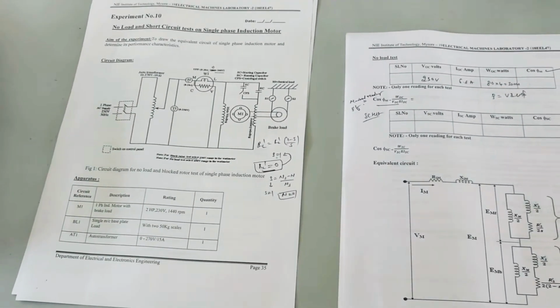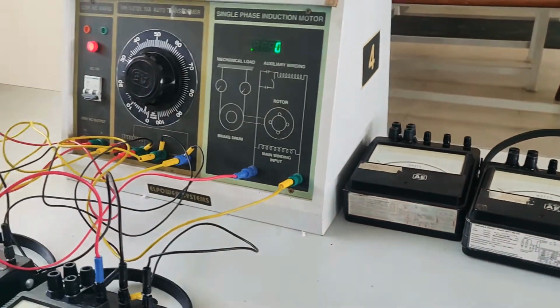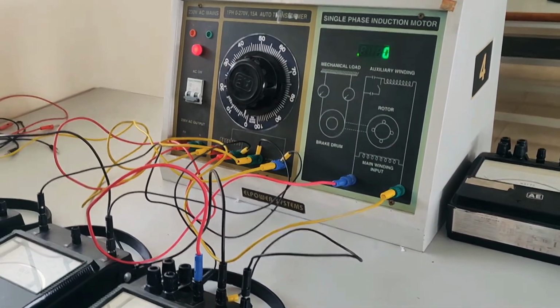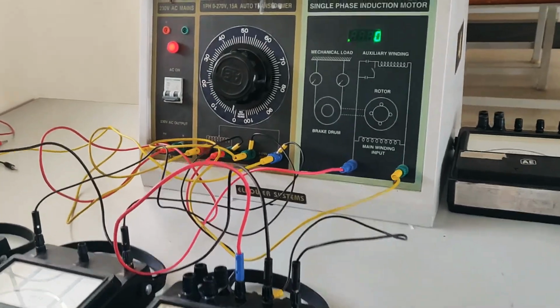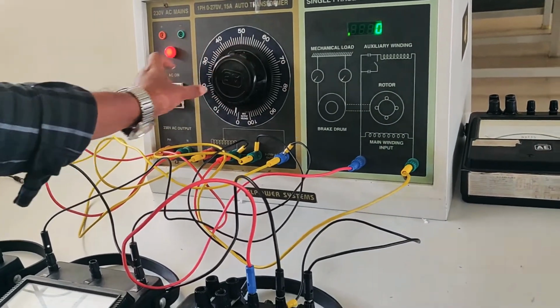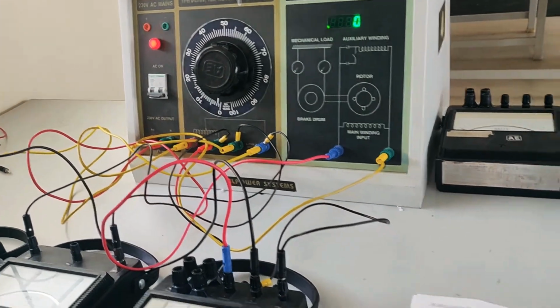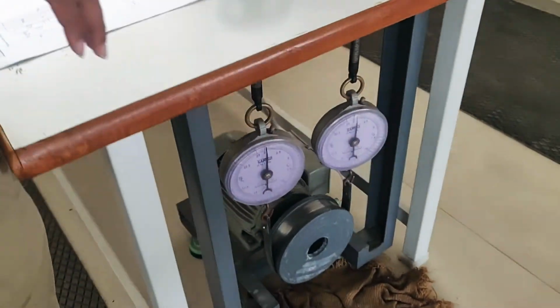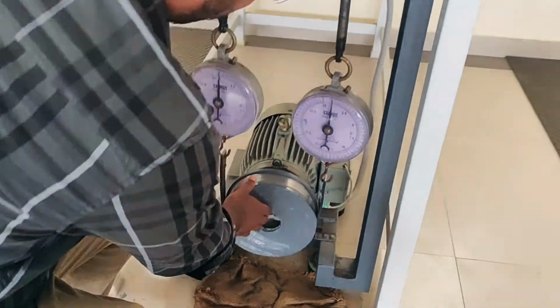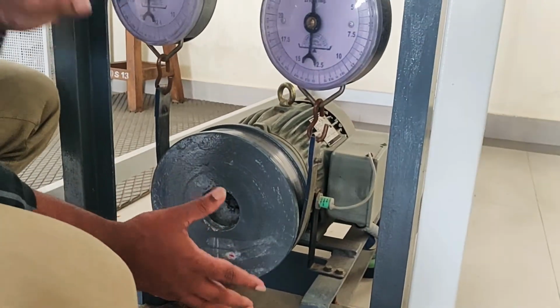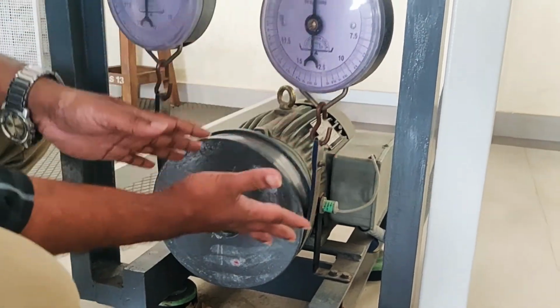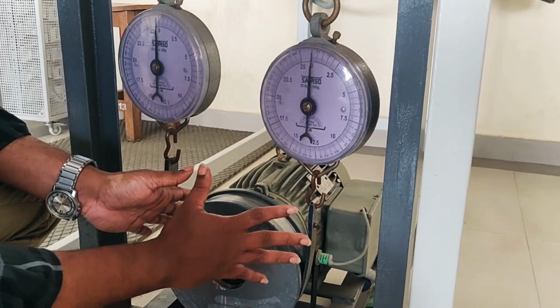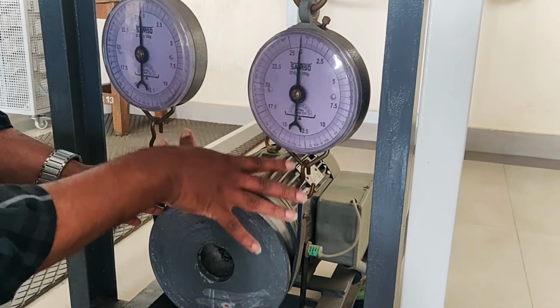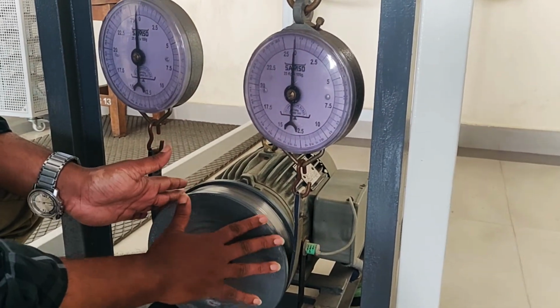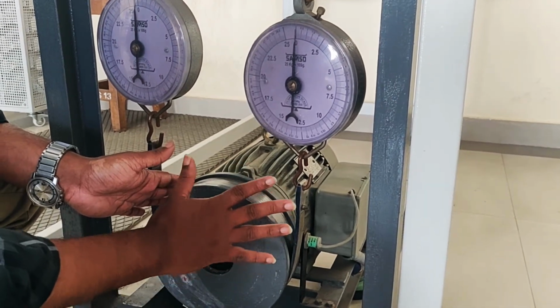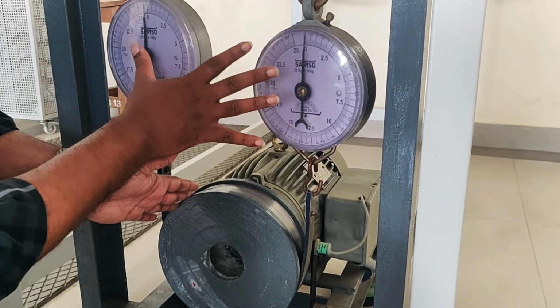So let us see how to conduct the short circuit test. It is almost similar to the short circuit test you have done for a transformer. The first thing is to ensure that the auto transformer is at 0 and the MCB is off, and then you have to block the rotor. You can block it manually, otherwise you can apply the load such that the rotor is not allowed to rotate. We can apply maximum load to the rotor so that it is blocked. Before applying the voltage, first you have to block the rotor.